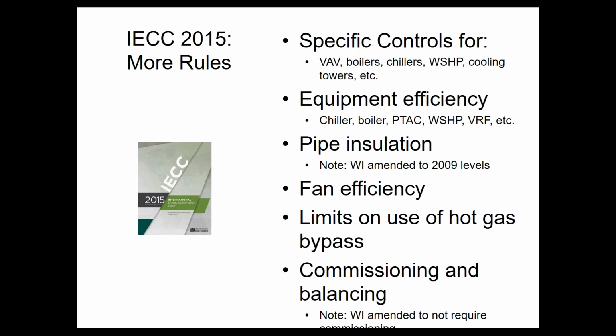I will note on that, Wisconsin made an amendment to not update that portion of their code. Wisconsin's going to stick with the 2009 IECC levels. Illinois is on the 2015 levels of that book. There's requirements for fan efficiency. That's like a whole webinar in itself on all the rules on how much static you're allowed to have on your air handlers and that kind of stuff. There's tons of limits on hot gas bypass. You should try just in general to avoid having any hot gas bypass if you can. There's a couple different sections of the code book you're going to have to go back in and check out. We'll talk about that in the coming weeks on these webinars as well.